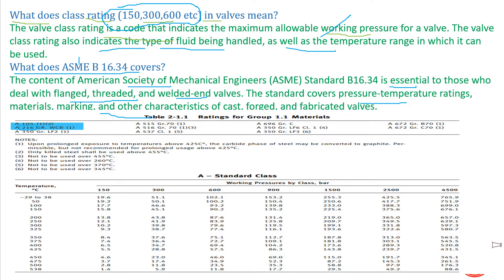For example, take material ASTM A216 Grade WCB — a cast material. To see the temperature and pressure rating, let's select the Class 150 pressure rating. In a temperature range of minus 29 to 38°C, it will be able to sustain a working pressure of 19.6 bar. For a Class 300 rating valve, in the same temperature range, the pressure it can sustain grows to 51.1 bar. This is how we select the pressure-temperature rating for valves in ASME B16.34.